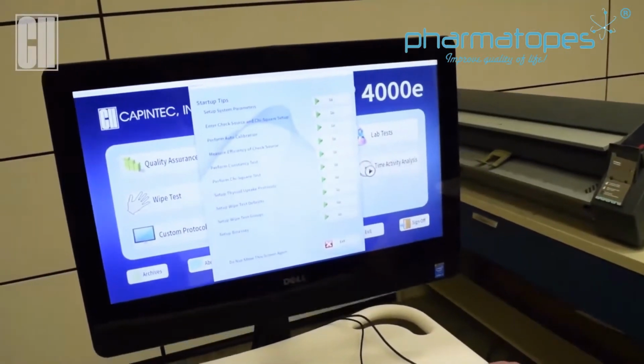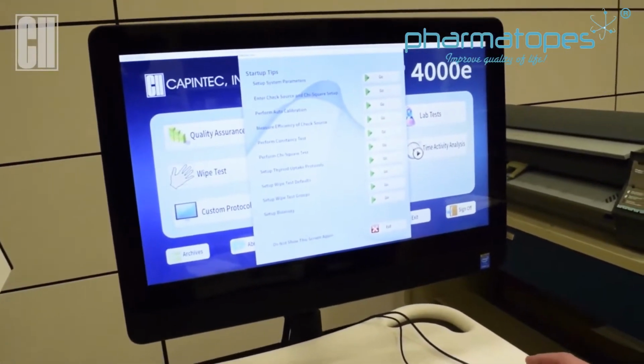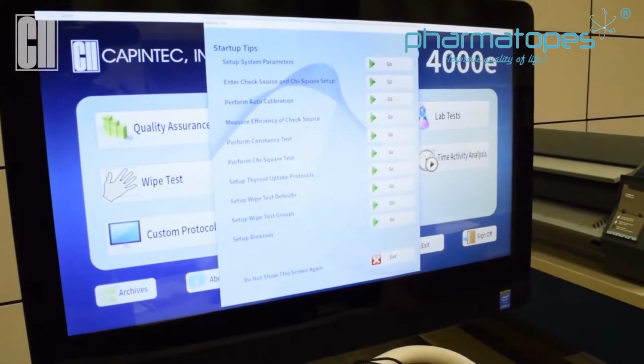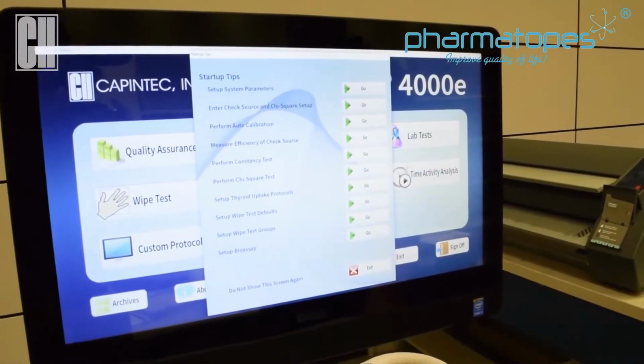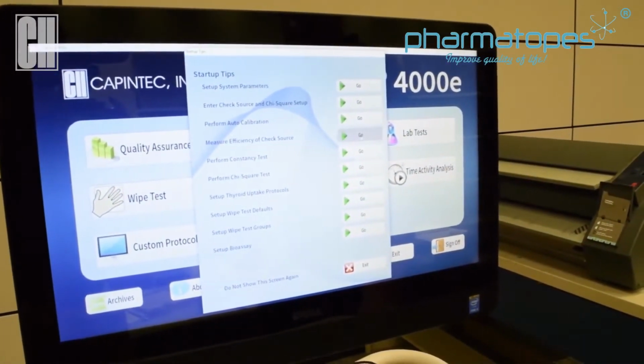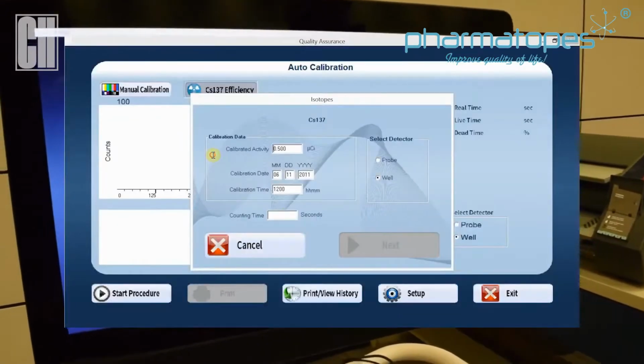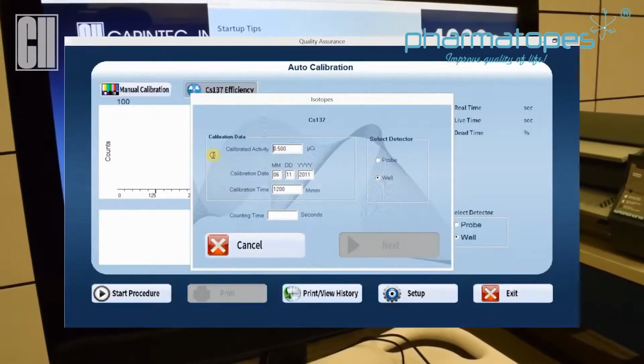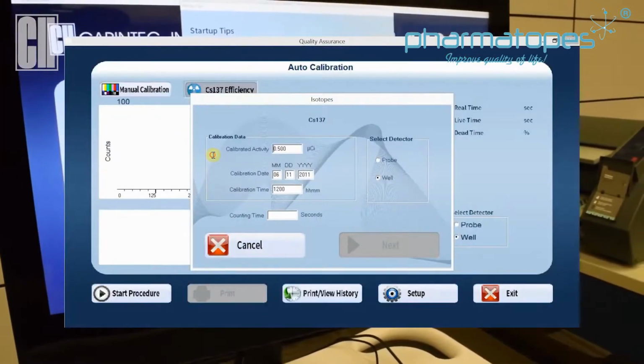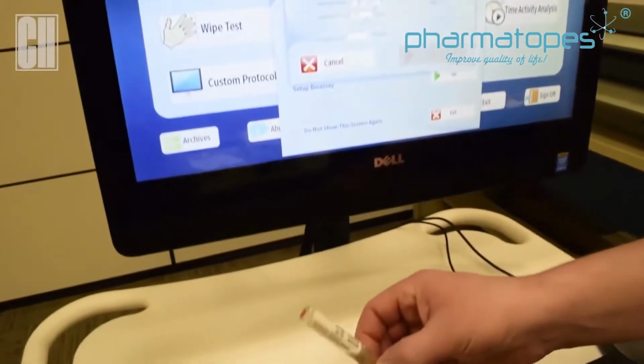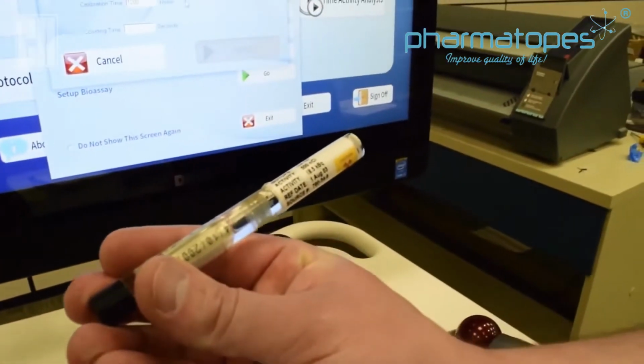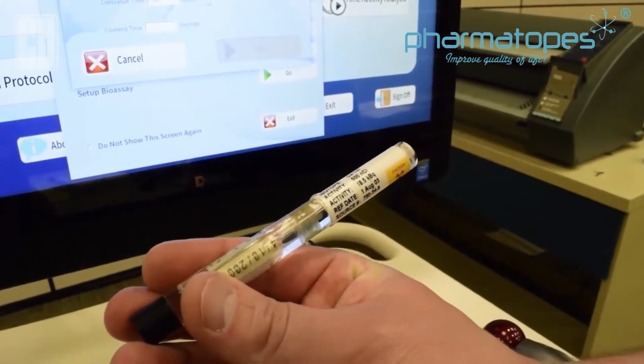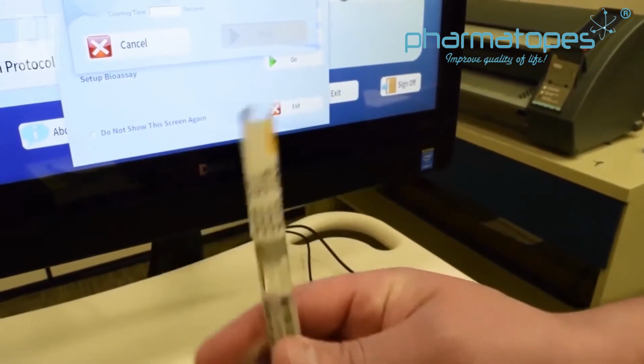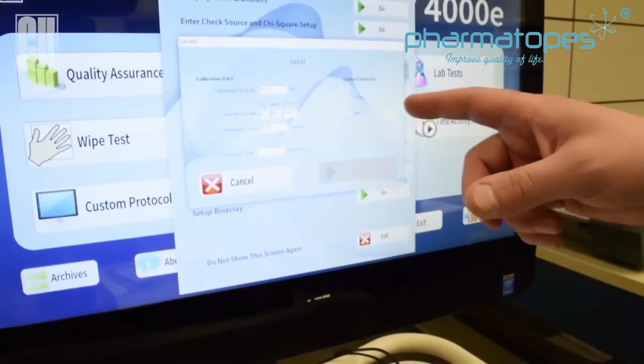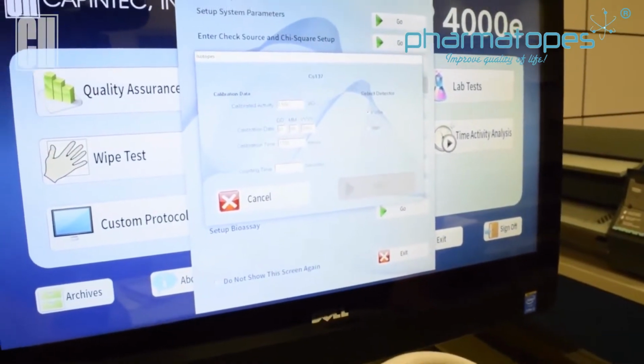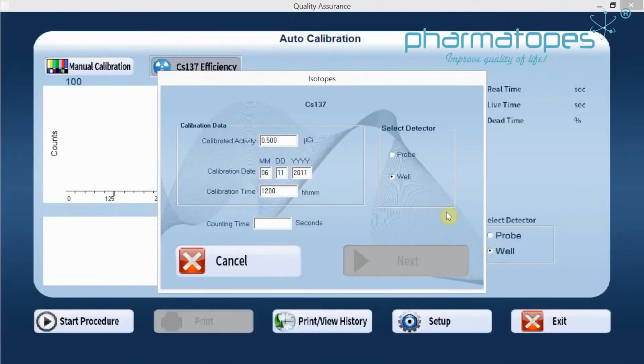To measure the efficiency of the check source, we'll click on go, and we want to verify that the source information is still matching what we have on our test source. Again, that should match what's on our label. Once we confirm that it matches, we want to select the detector that we're going to measure the efficiency for.